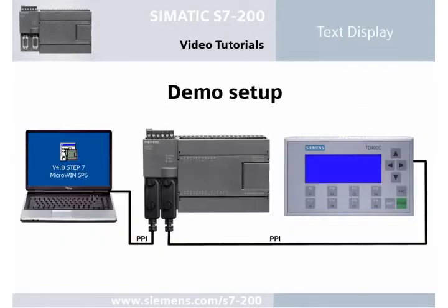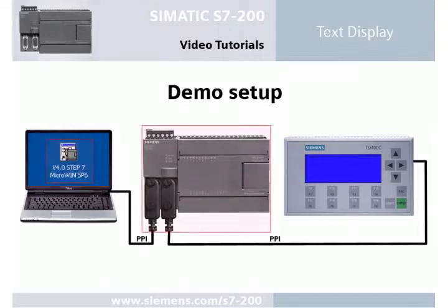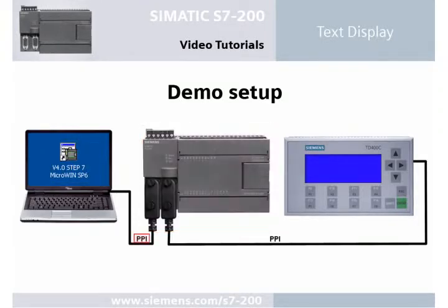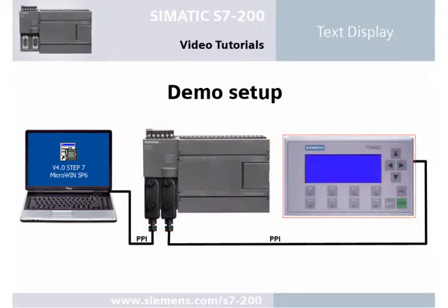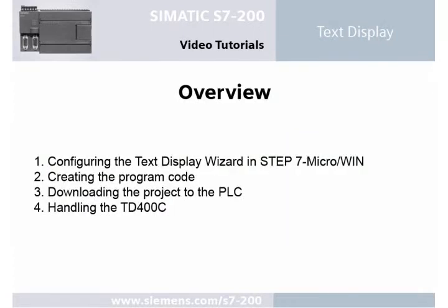In STEP 7-Micro/WIN, the program code for the text display is generated with the aid of the text display wizard and is downloaded to the S7-200 controller via the PC/PPI cable. The communication between the controller and the text display is also via PPI. The task includes the four steps described below.